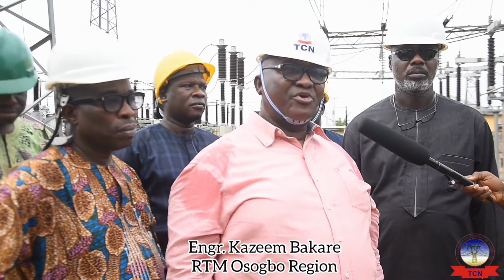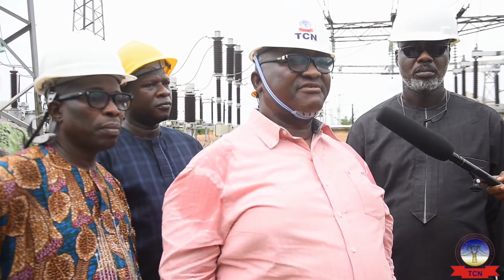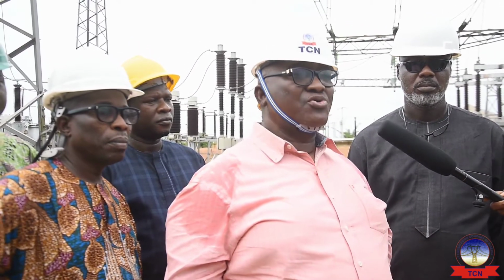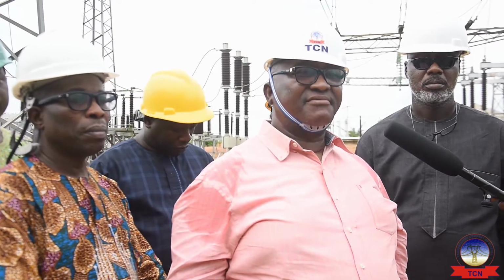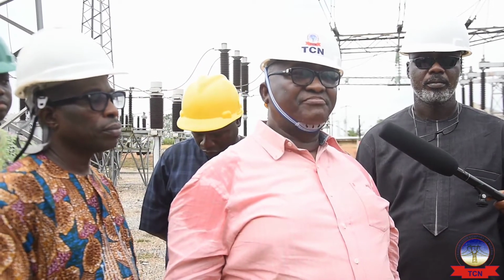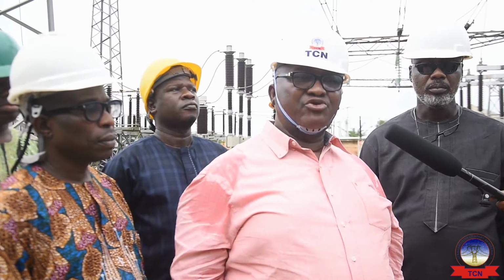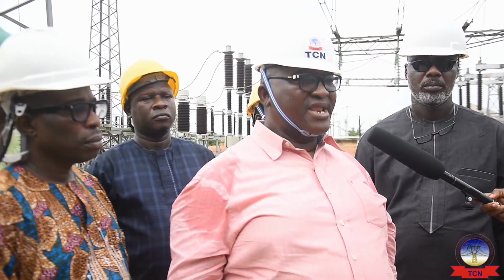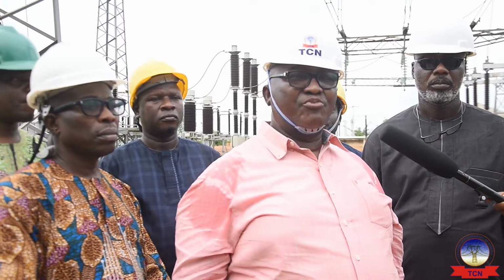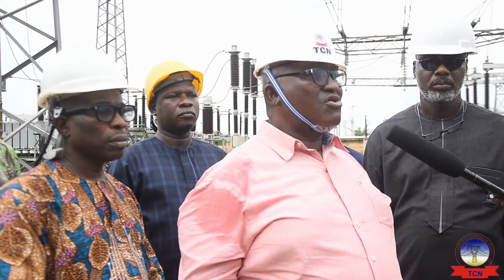Recently, we have been having a lot of problems, particularly protection problems. When there is a fault in far away Isheyin, it will upset our system either at Osogbo or at Ibadan North. In this station, there are 3 infeeds. We have one from Ibadan North, and we have another from Osogbo. We have the one going to Isheyin. All of them are emanating from the 132 kV bus bar here. Before now, there were no circuit breakers and there was no protection. So faults here will go as far as either Ibadan North or Osogbo.